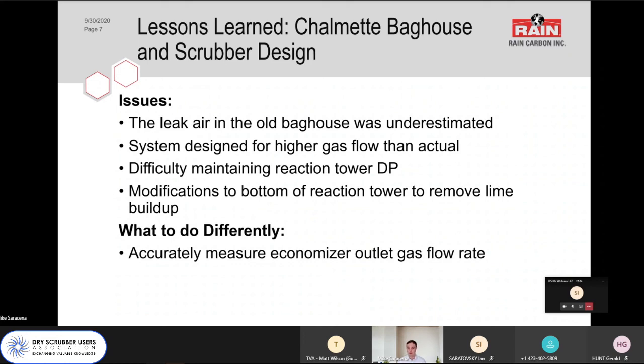That directly resulted in issues maintaining reaction tower differential pressure. So the reaction tower is a fluidized bed of lime. Without enough differential pressure, you will, what we call, lose the bed, which is where there's maybe 5 to 10 tons of lime in there that drops down to the bottom. All the lime has to be cleared out. You have to shut down the energy side of the plant until you can clean it out. It's really quite a problem. And at lower facility feed rates, this is happening more and more frequently.